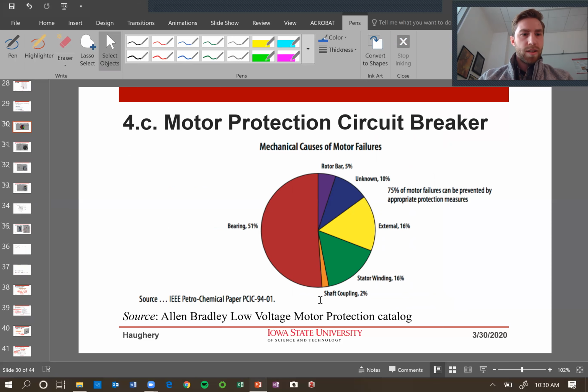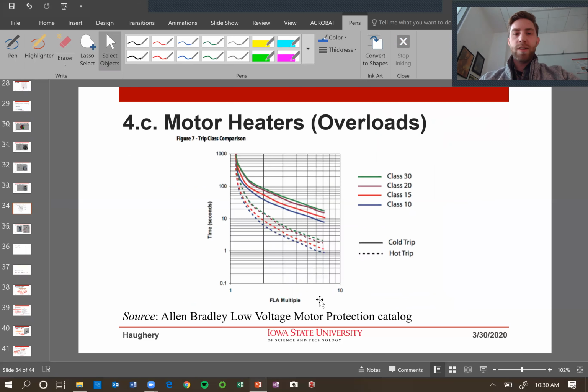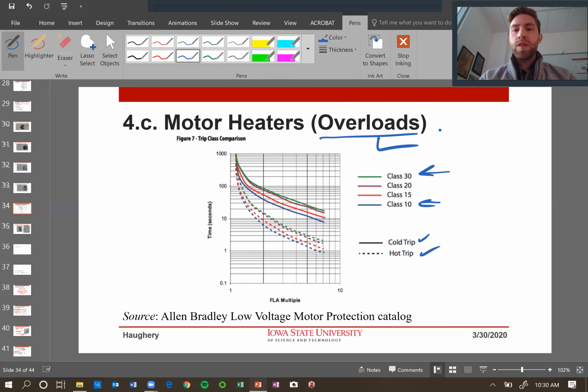Then we looked at motor overloads or heaters, and there's a similar process to interpreting their trip curves. The one difference we have here is we have classes, and so class 10 will trip faster than class 30s, and we have a cold trip versus a hot trip. So if it's hot out, that's going to trip that overload much quicker. And if it's cold out, a lot of this tripping is based on the thermal temperature of the element inside that overload.